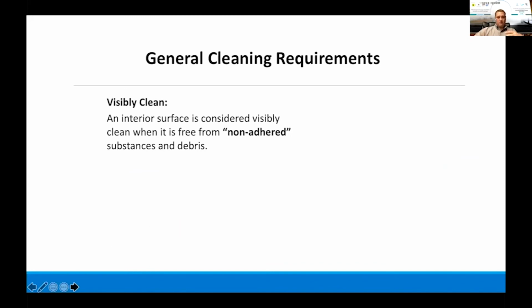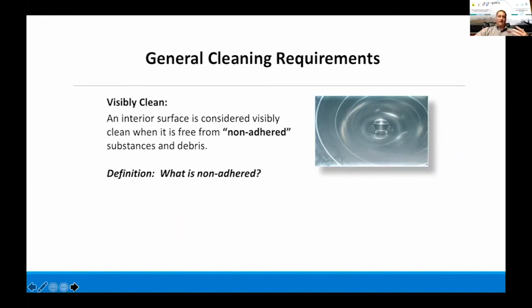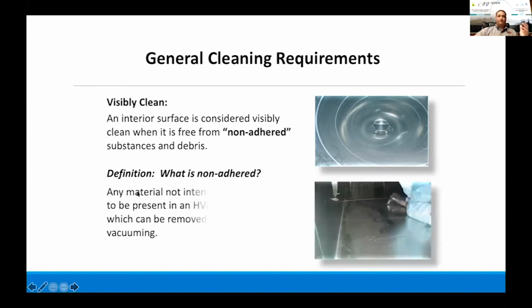Within the ACR, there are certain terms that will be used, and NADCA did a wonderful job of clarifying these things to make sure there was no misunderstanding as to what they mean by certain items. So in this case, visibly clean. An interior surface is considered visibly clean when it's free from non-adhered substances and debris. Definition, what is non-adhered? Any material not intended or designed to be present in an HVAC system, which can be removed by contact vacuuming. If you see here, this individual is inside of a duct with a vacuum, vacuuming up this debris that is there. It's not supposed to be there.